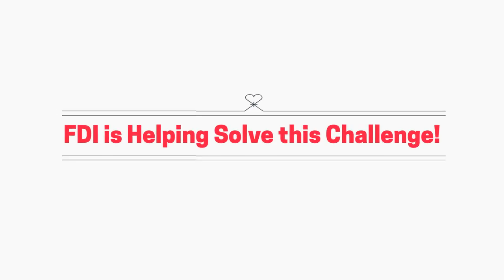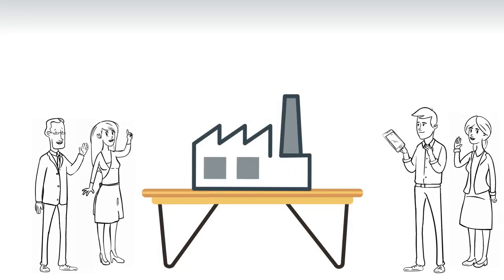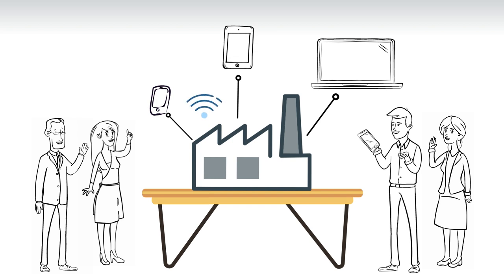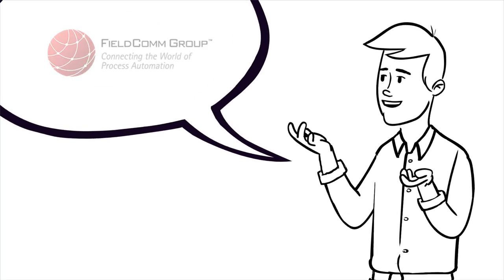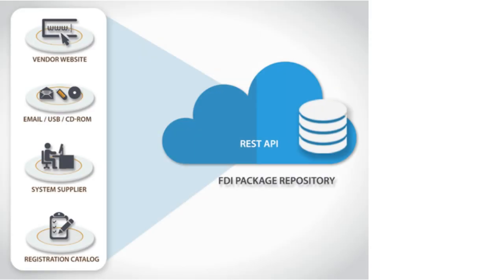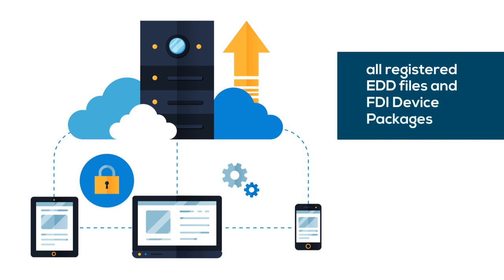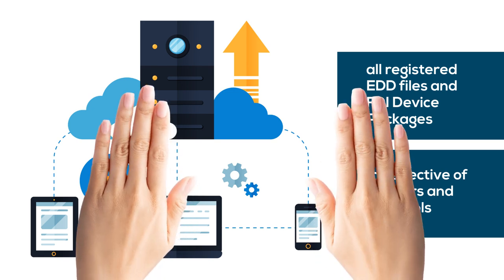FDI is helping solve this challenge. The core of device revision management lies in keeping the system and handheld field communicator aligned with the latest devices and revisions across various device types and manufacturers represented on-site. FieldComm Group has developed an innovative solution to simplify device management: the FDI Package Repository. It offers a cloud-based solution that can act as a single distribution source for all registered EDD files and FDI packages, irrespective of vendors and protocols. There are three primary benefits provided by the FDI repository.